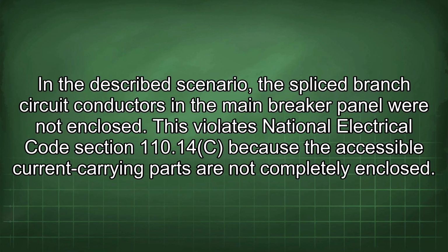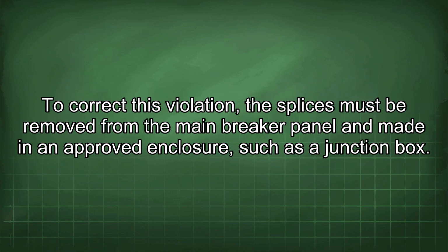In the described scenario, the spliced branch circuit conductors in the main breaker panel were not enclosed. This violates National Electrical Code Section 110.14(C) because the accessible current-carrying parts are not completely enclosed. To correct this violation, the splices must be removed from the main breaker panel and made in an approved enclosure, such as a junction box.